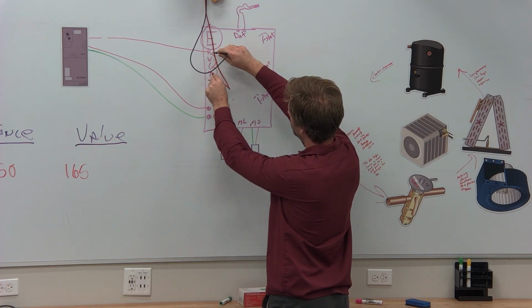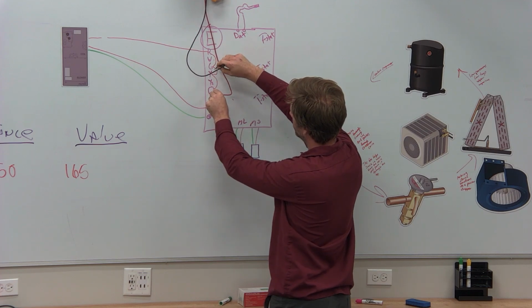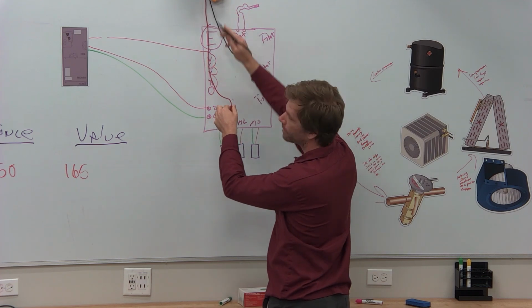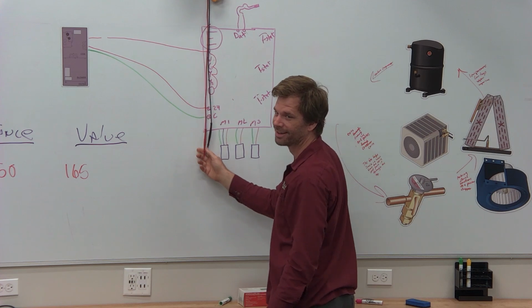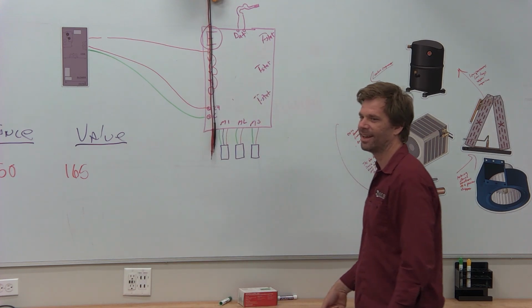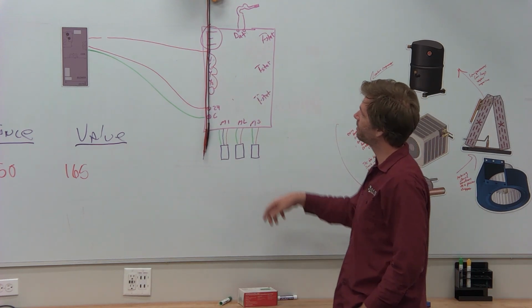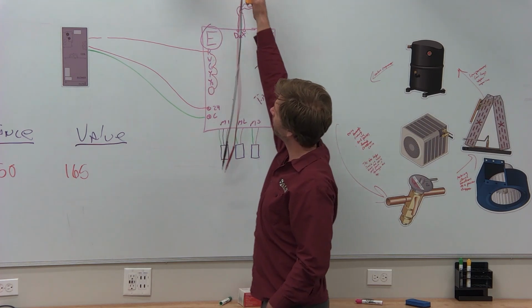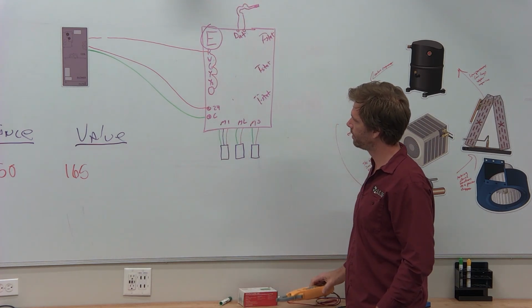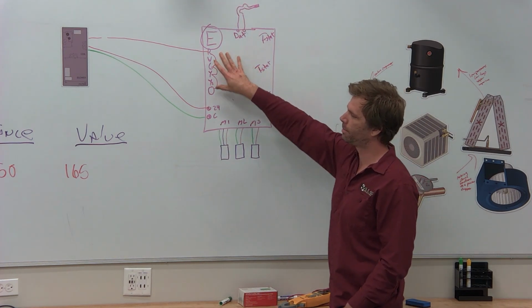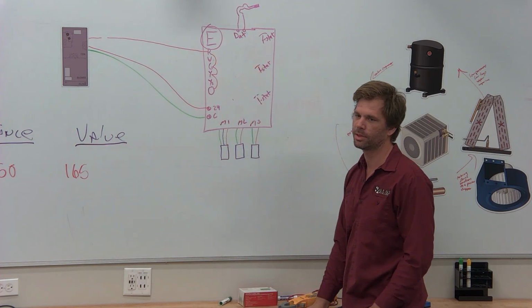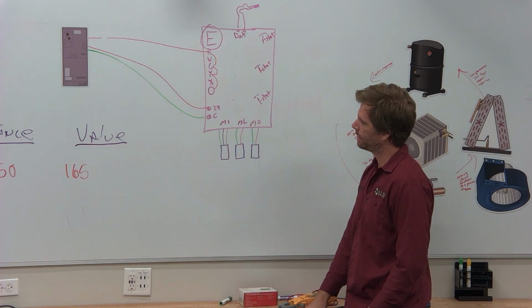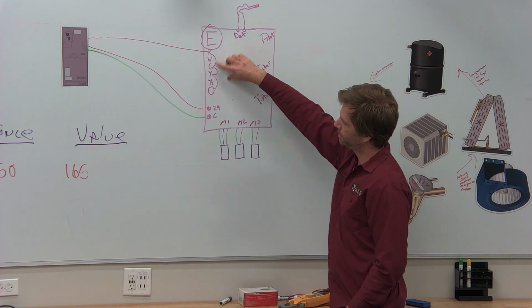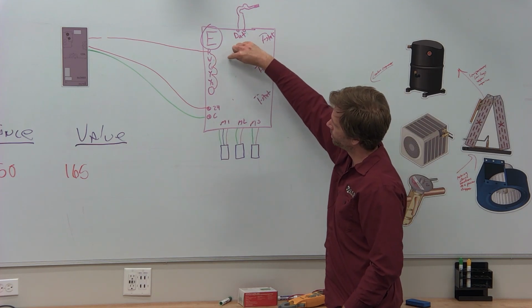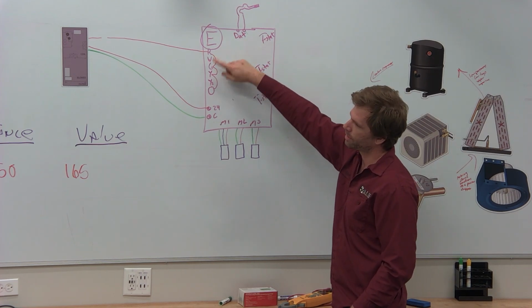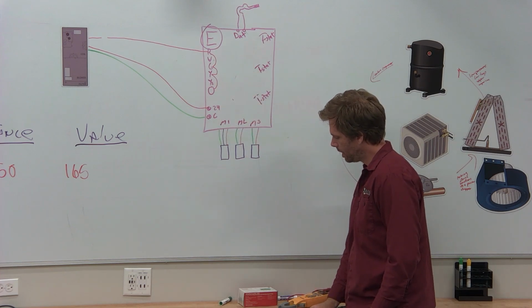Okay, maybe we'll do this. Still, it's still showing me 0 volts up there. And so the frustrating experience often is, like, okay, there must be something wrong with the board, because everything else is doing its job, but I'm not getting power on these terminals like I'm supposed to. And it's because none of this power gets sent on the terminals. It just controls the switches that open and close connecting R to here.